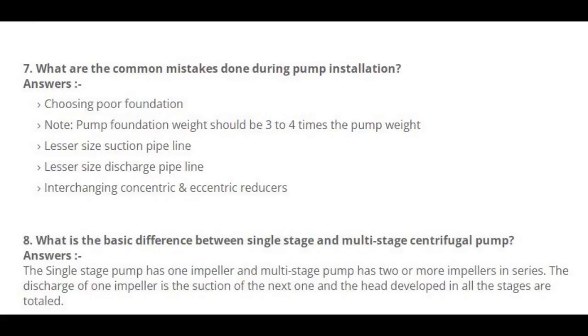Number 7: What are the common mistakes done during pump installation? Choosing a poor foundation. Note: pump foundation weight should be 3 to 4 times the pump weight. Lesser size suction pipeline. Lesser size discharge pipeline. Interchanging concentric and eccentric reducers.